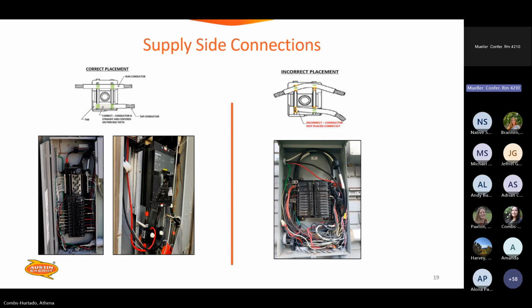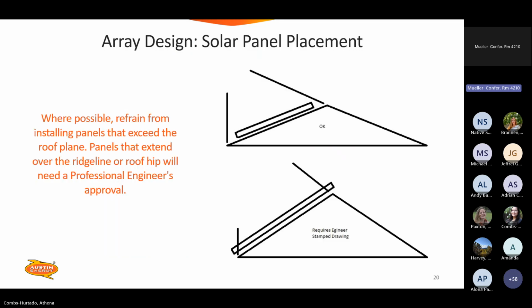So 312.8 in the NEC. That's basically you need no more than 75% of that space to be occupied, which is a hard number in the field to assess. But I've heard it said that basically, if you have to put the dead front on and it takes actual pressure to close that dead front on one of those panels, you're probably breaking the rule. So that's a rule of thumb on that one. Next.